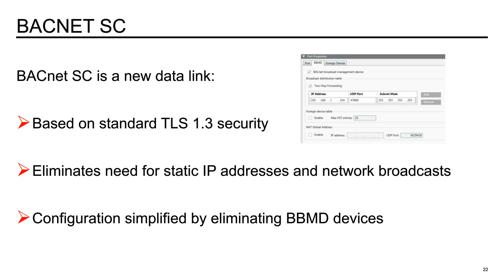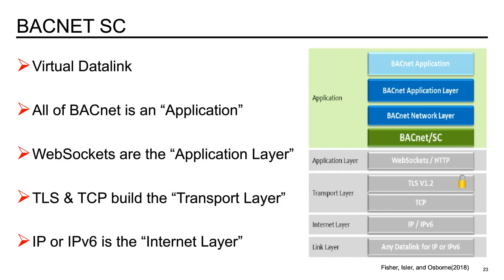Basically, BACnet SC is a virtual data link that bundles the BACnet network and application layers to become an application. The application is linked to the application layer with WebSockets through HTTPS. A WebSocket is a communication protocol providing a two-way communication channel over a TCP connection. The WebSocket keeps the connection open and allows the client and server to securely send and receive information.